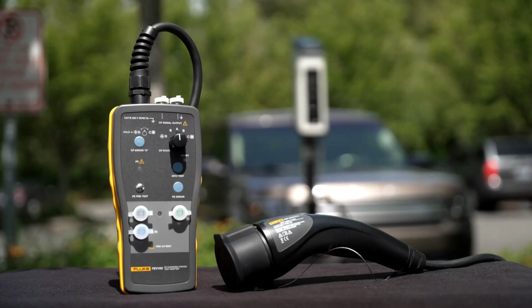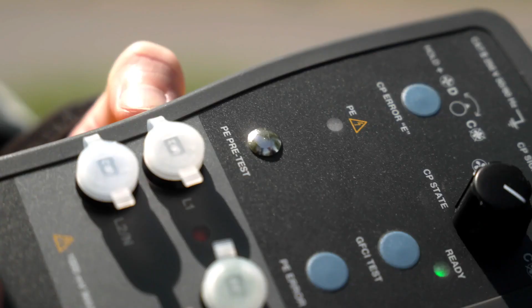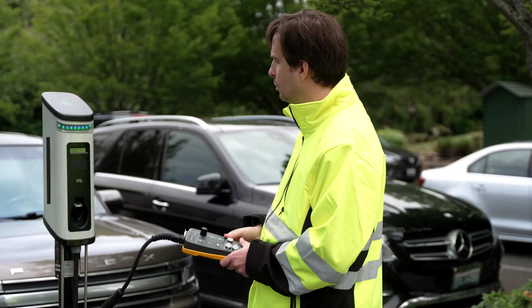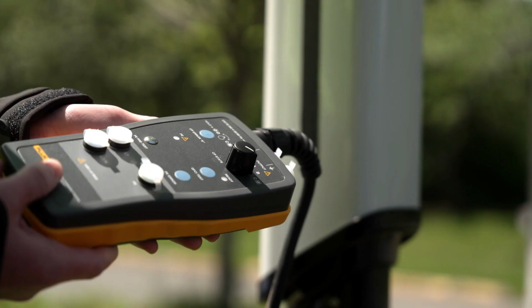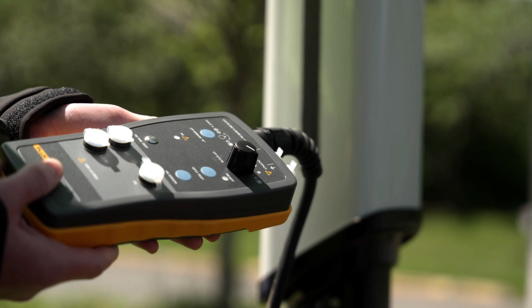The Fluke FEV100 EVSE test adapter simulates the presence of an electrical vehicle to enable you to test the function and safety of an AC Level 2 charging station. The test cable is the interface for cables of stations that have a Type 1 plug. First, perform a pre-test grounding safety check to ensure the charging station is correctly wired and safe, and that the protective earth is functioning properly. No LED illumination means everything is working correctly.